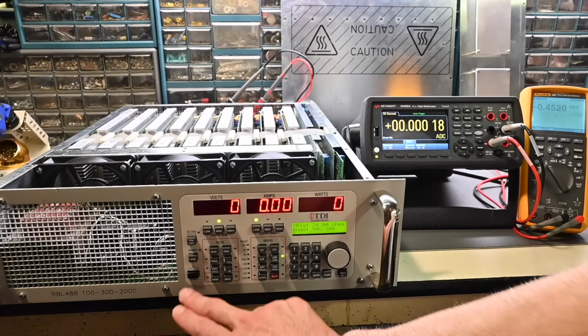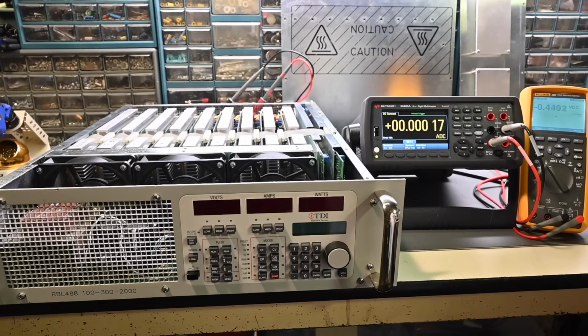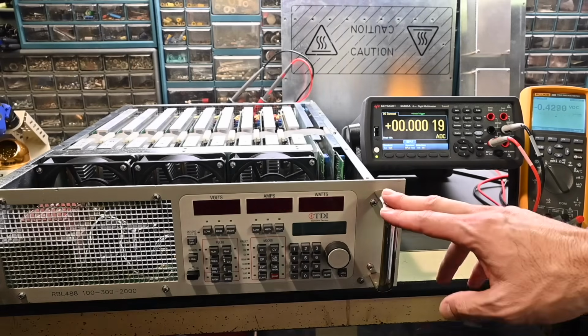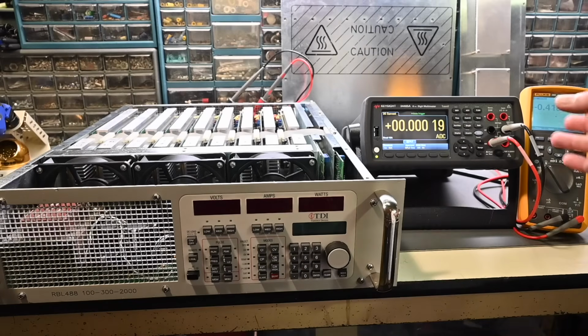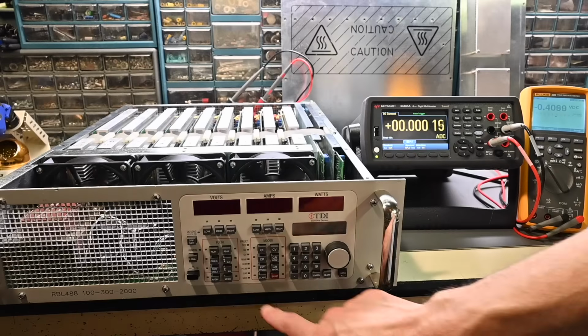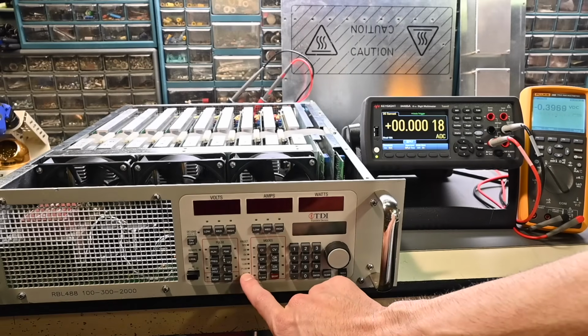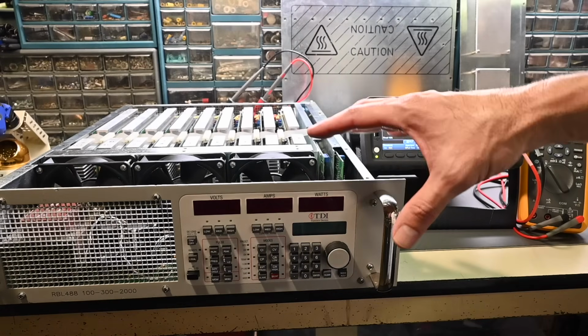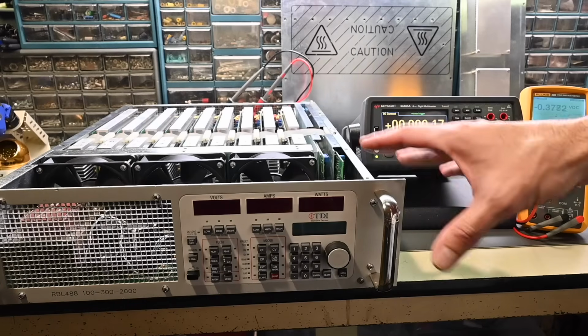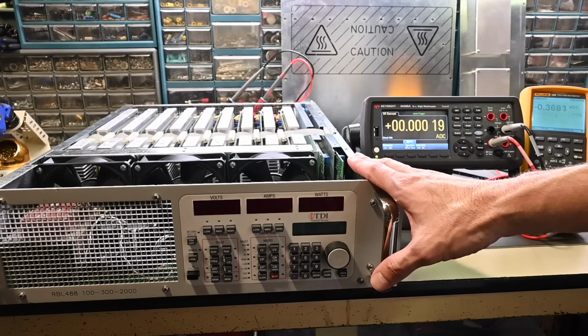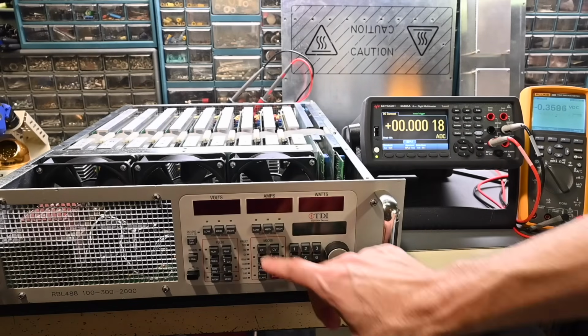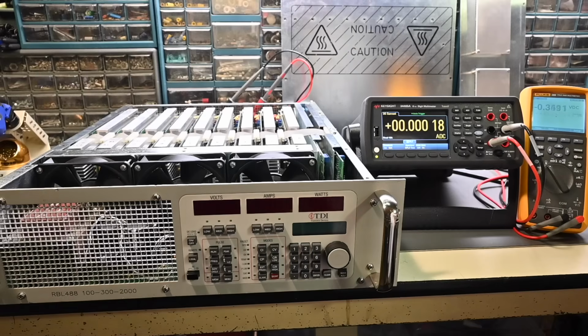So, if you try to turn the electronic load on and there is no voltage, or the voltage falls too low, you'll end up getting this saturation light that comes on. Basically means that all the devices, all those power FETs, are completely saturated. They can't be driven any harder. So, you know, quite a few different faults that can be displayed right here for different situations.